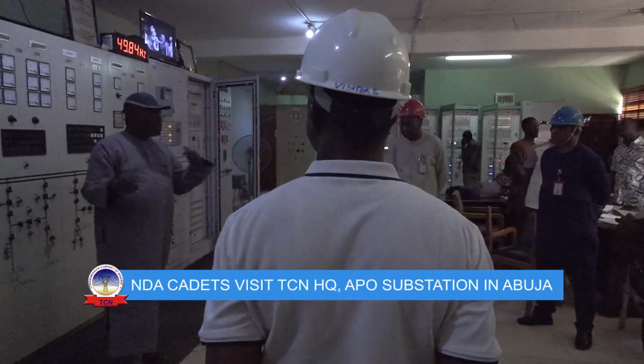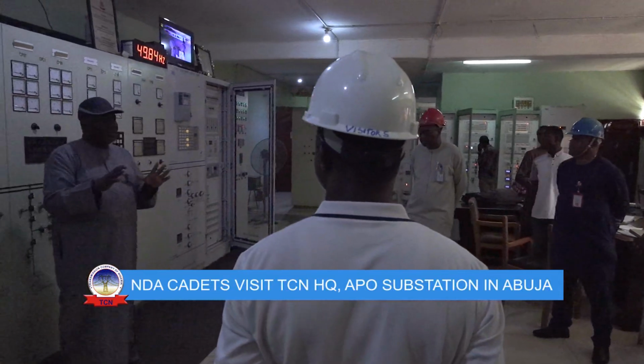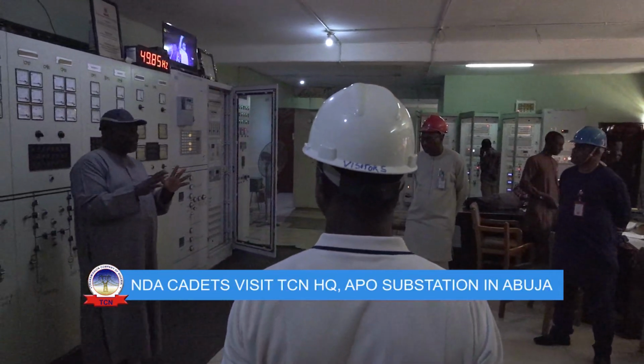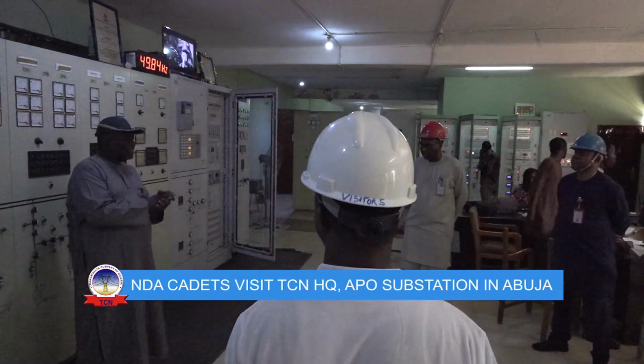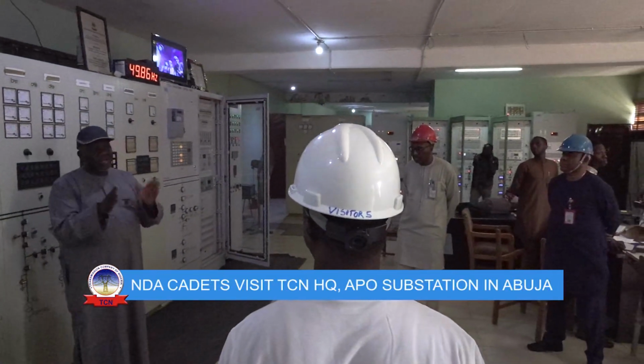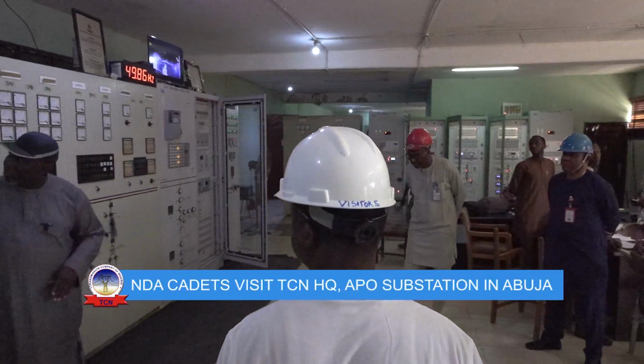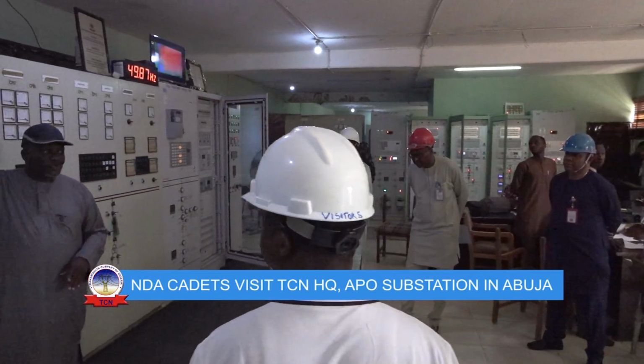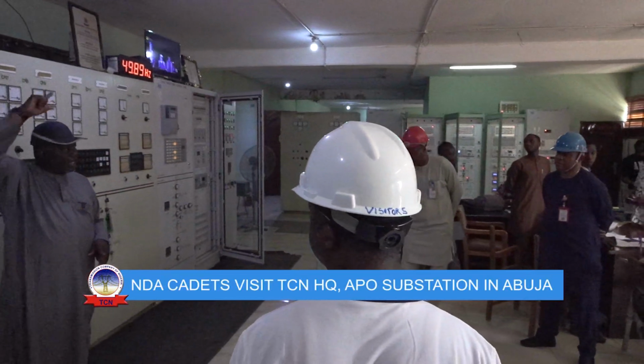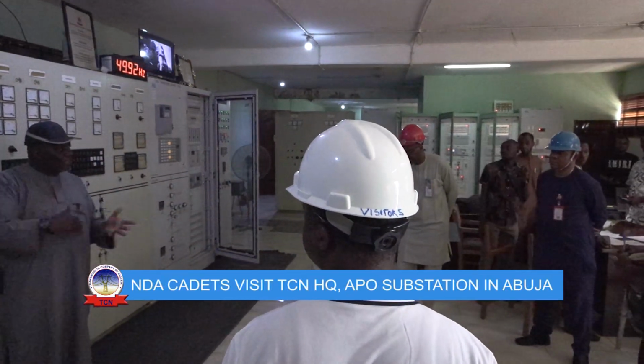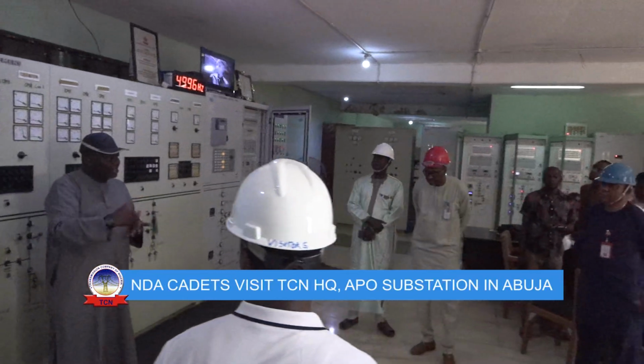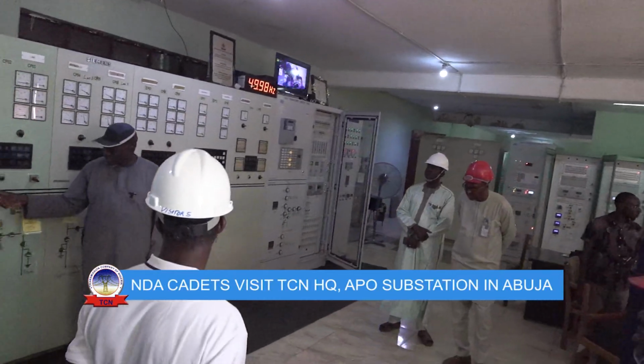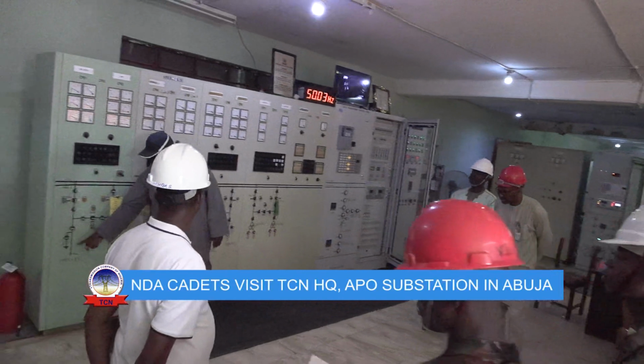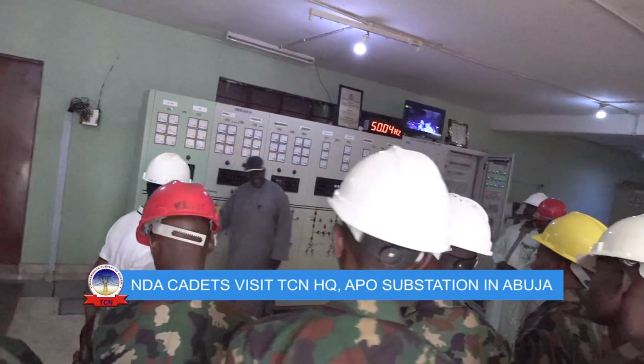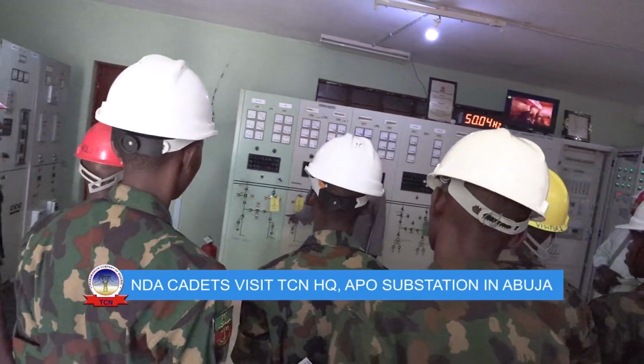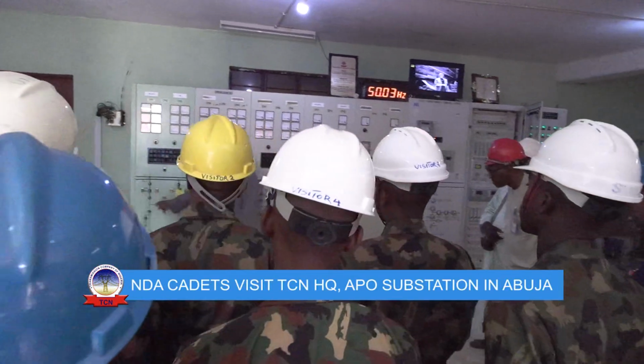Ideally, the kind of system we have here in TCN is what we call a 1.5 breaker arrangement. Like this one here, this is a line - this line goes to Akwanga. On each way you have a tee-off at Karu, Keffi, Akwanga. These are the buses, bus 1 and bus 2. This is a line bay, then this is the tie bay. That is why we call it a 1.5 breaker arrangement.